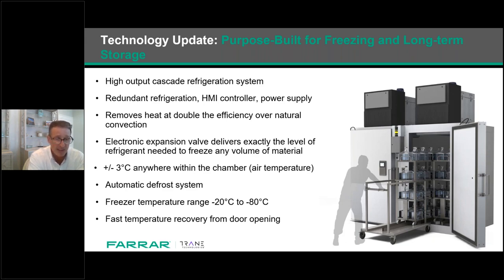So the FARRAR forced air solution presented provides a wide temperature range control. So this is where, unlike a cold wall freezer, typically designed to operate between minus 50 and minus 80, the FARRAR purpose-built freezer can operate at a wider range, minus 20 to minus 80, with full redundancy. And this is where it's key, right? So everything is redundant. We have two refrigeration systems. We have two HMI controllers. We have two electrical power supplies that power each refrigeration unit system. And the temperature uniformity, and this is where it's huge, right? So the uniformity within the chamber is plus or minus 3 degrees C at control set point with an empty chamber. So something else to keep in mind, this is the plus or minus 3 degrees C with no product inside the chamber. Next slide, please.